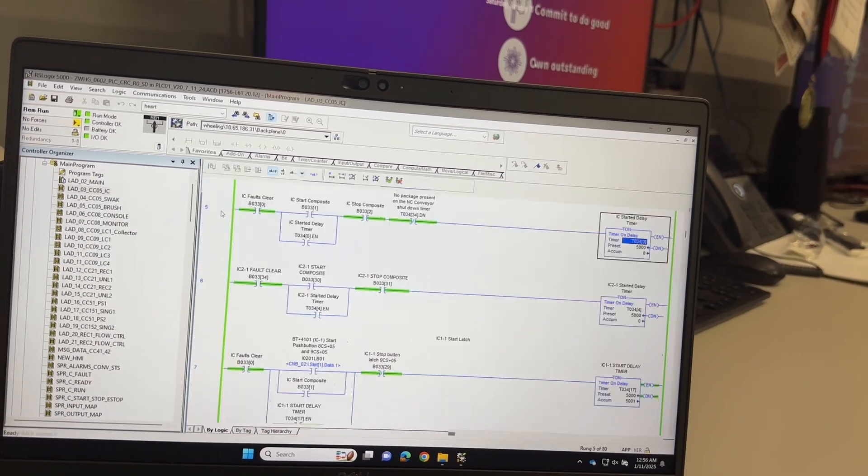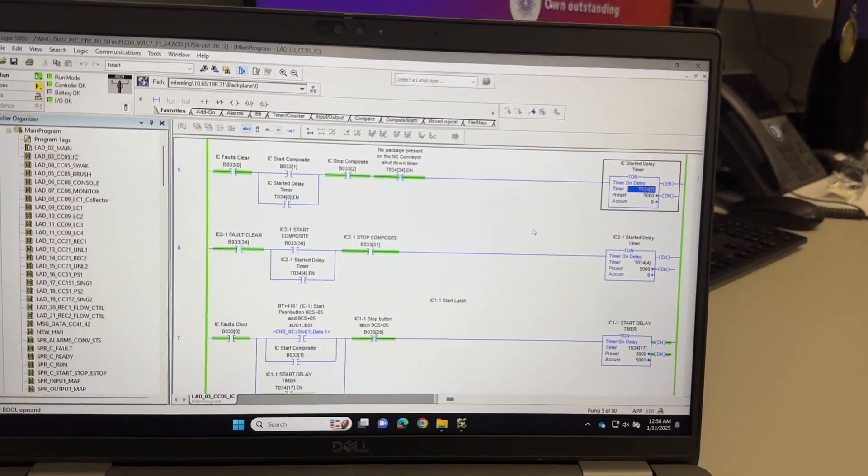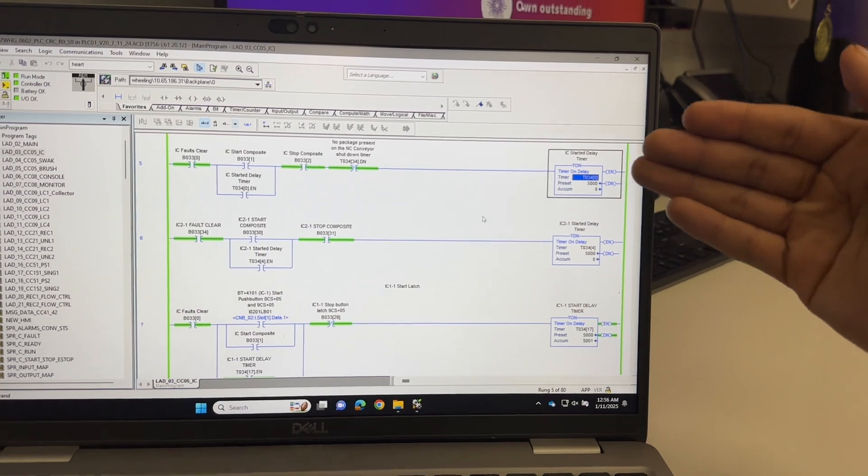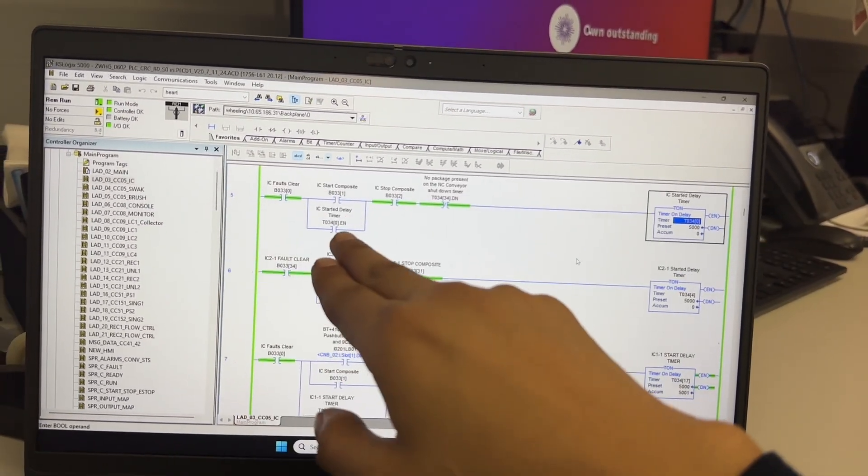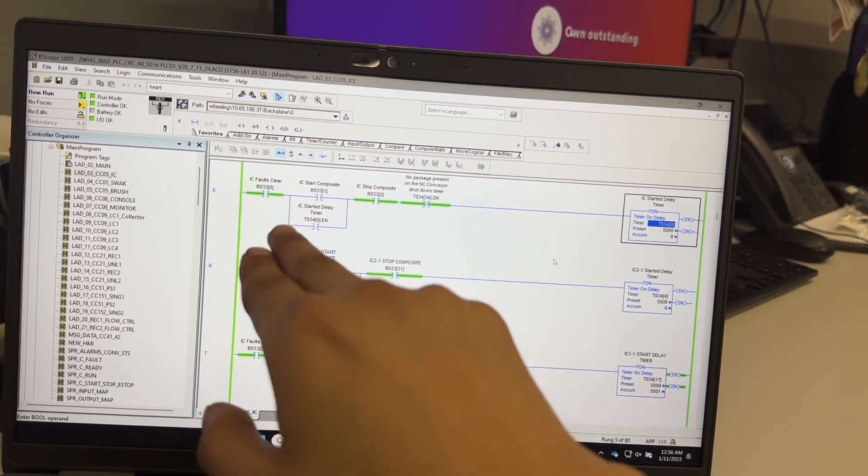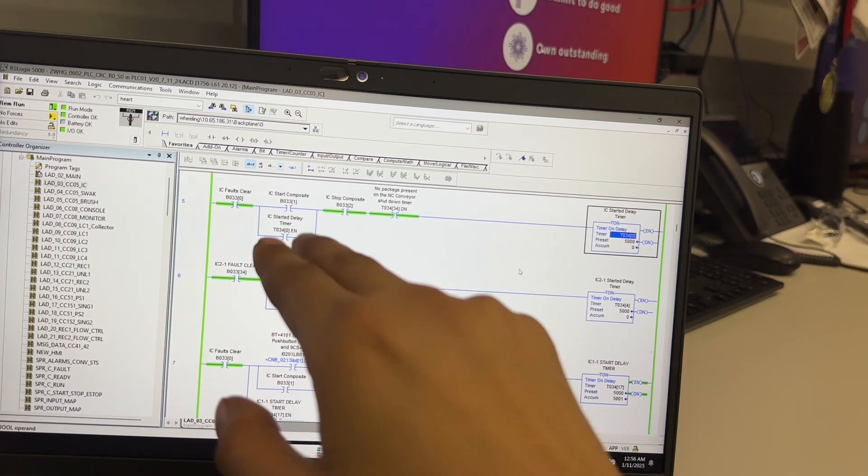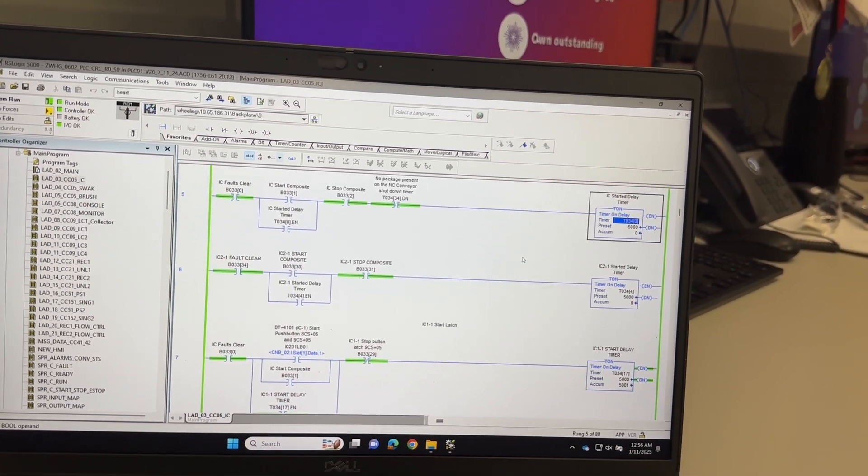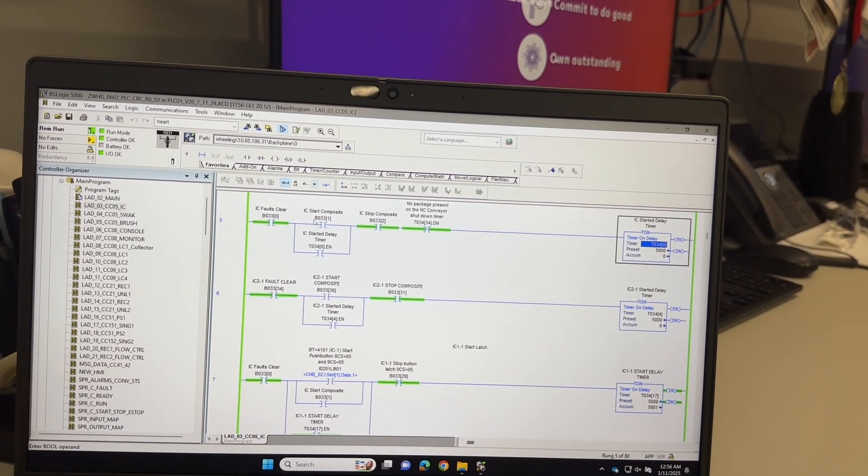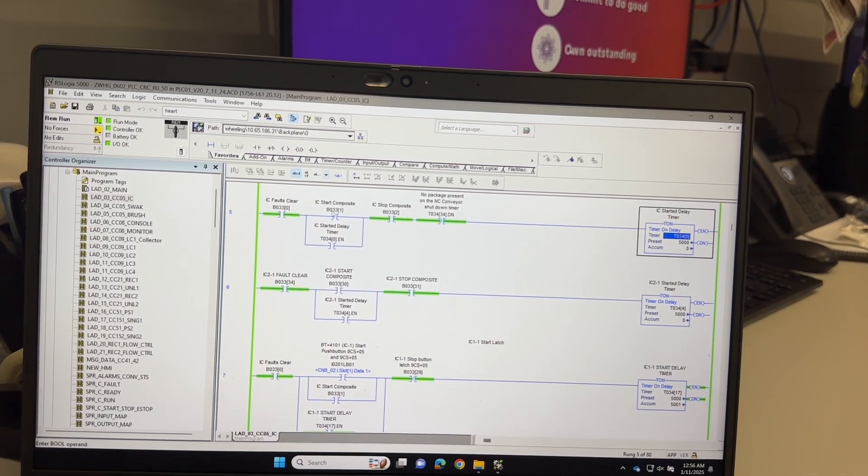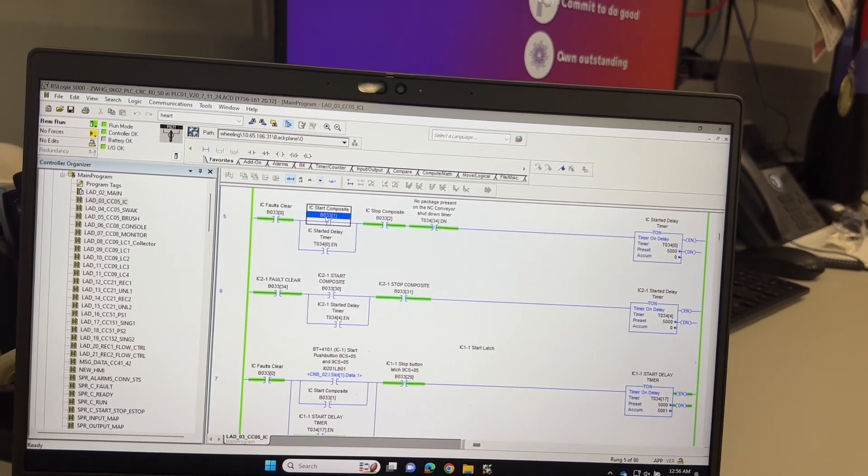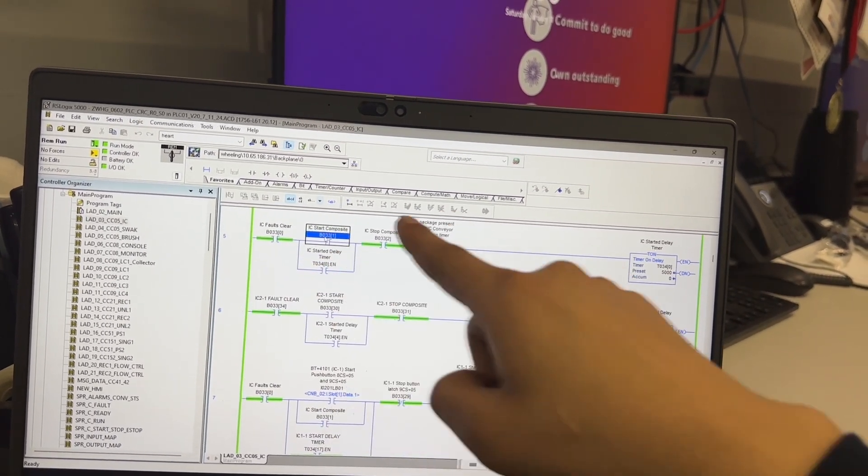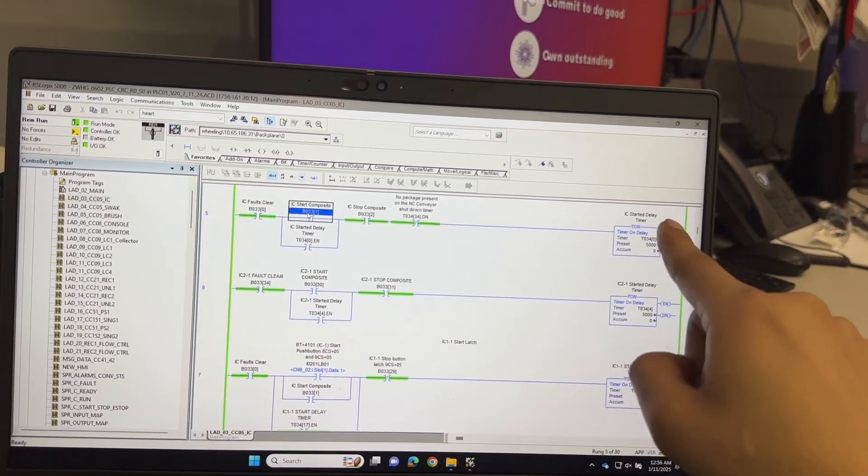But the important part is we go to the timer. Double click on the timer. Now right away it just took me to the timer. I know that this timer is not being turned on because there's a break in the continuity here. If I wanted to turn this conveyor on, I gotta follow this. Where is this coming from? This is an internal bit.